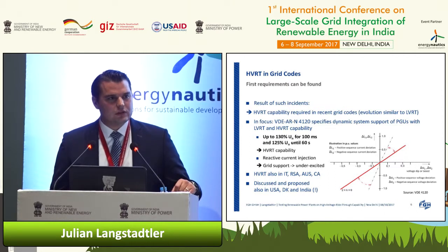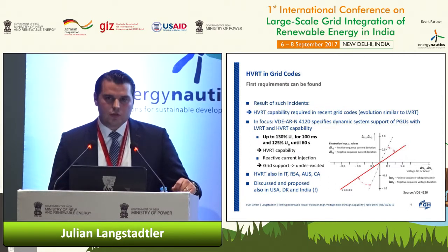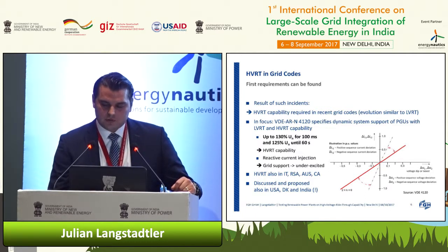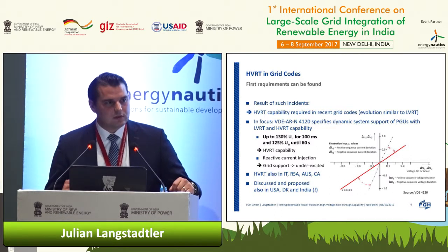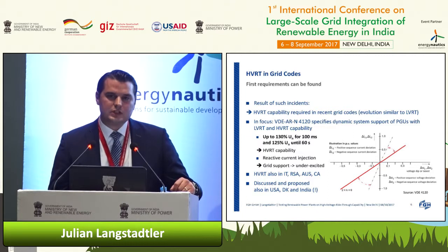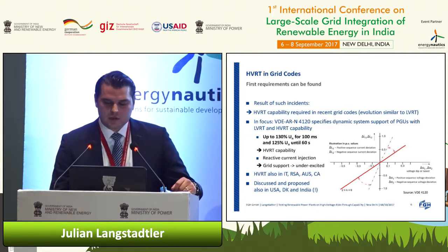However, we have an additional requirement that during the fault itself, the wind turbine or also the solar power plant must stabilize the system in its disturbance. So that means you have to inject a reactive current. And when we talk about overvoltage, you want to decrease the voltage and lower the voltage impact. So that means that you shall behave like an underexcited synchronous generator. So that means we are in the figure here in this area.